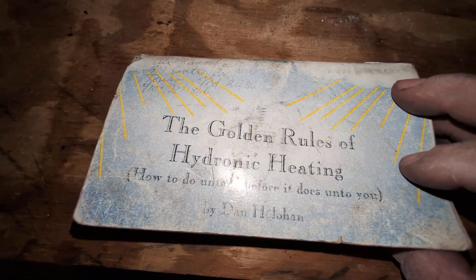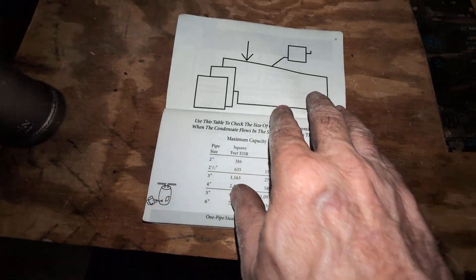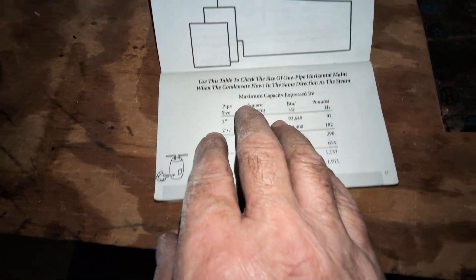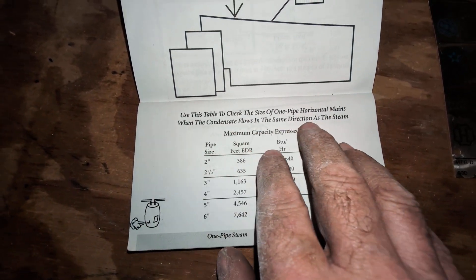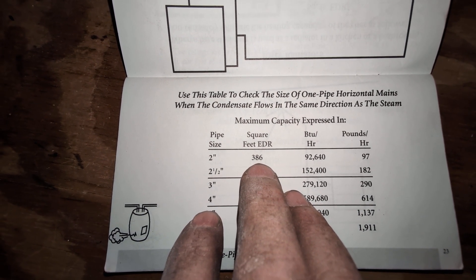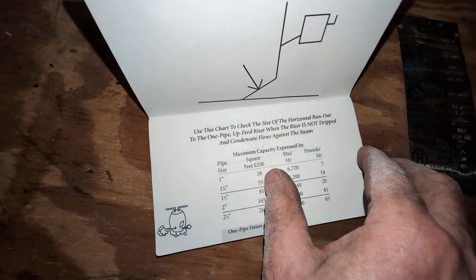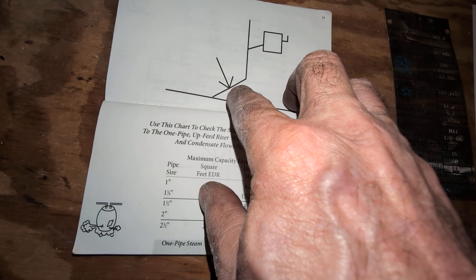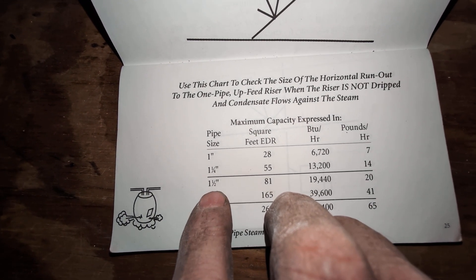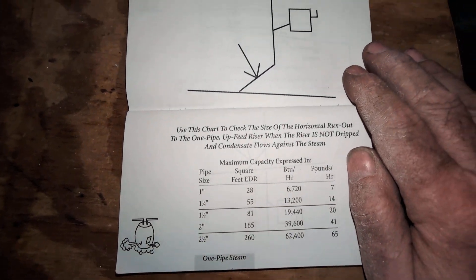This is a copy of the Golden Rules of Hydronic Heating — a first edition by Dan Holohan. What he's done is go back to the old charts from the late 19th and early 20th century. We see that when the condensate flows in the same direction as the steam main you're able to get 386 square feet down it. There's not even a chart for a counter-flow main — this is probably the closest one. And there you see it's an inch and a half; you're lucky to supposedly get 81 square feet out of there on a good day, and this is partially dripped.